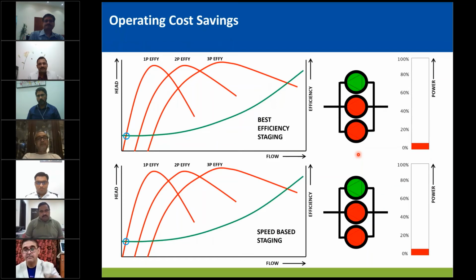Now, let's take a look at a comparison of how speed-based staging versus best efficiency staging works. So here I'm showing a speed-based staging curve at the bottom. On the top, you have best efficiency staging, and this is 3 pumps curve. This is 2 pumps together, one pump curve. And if you go up on the efficiency scale, you are much better. And this is the number of pumps working. Green is working, red is stopped, and power consumed.